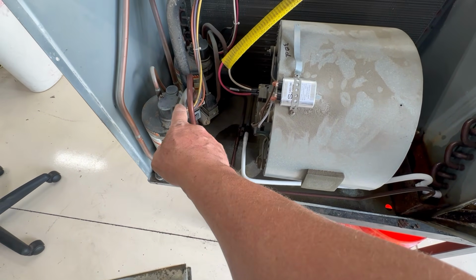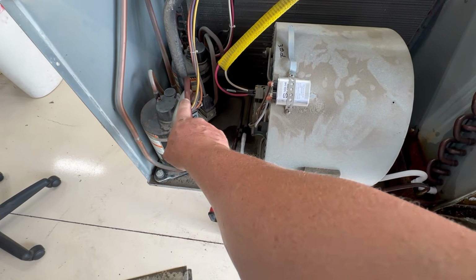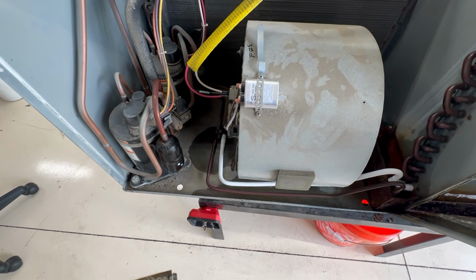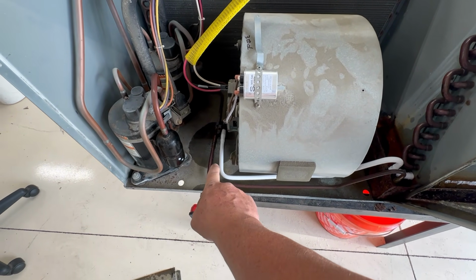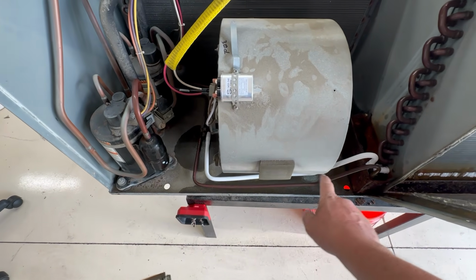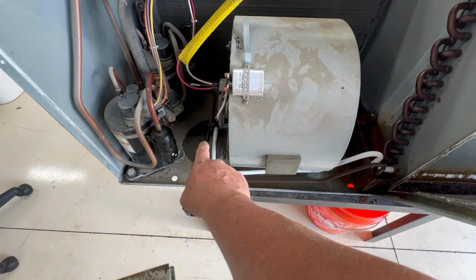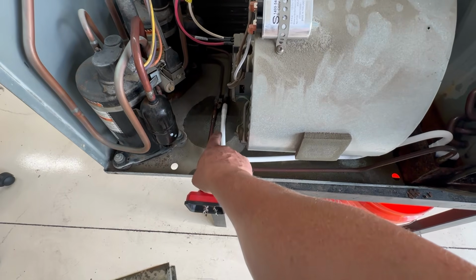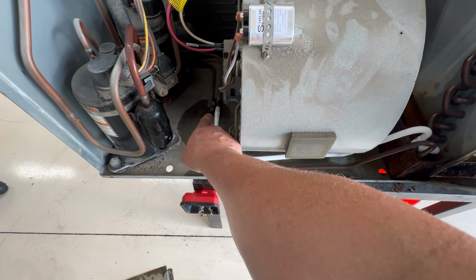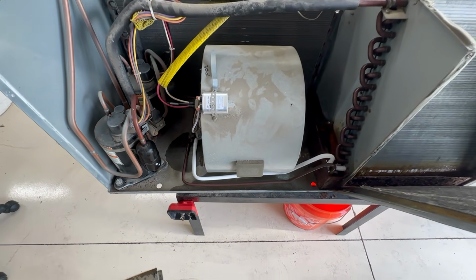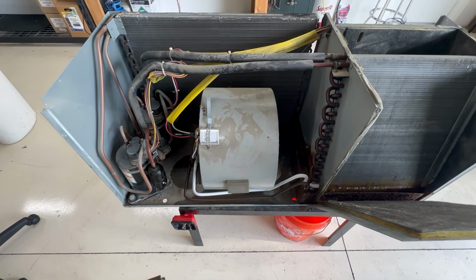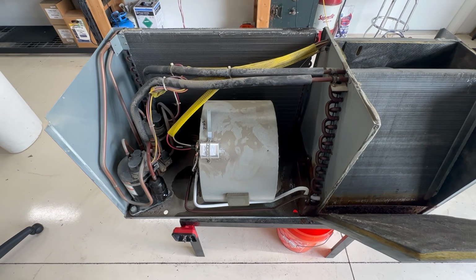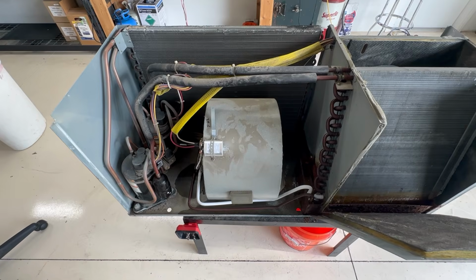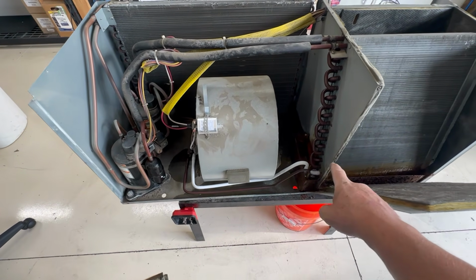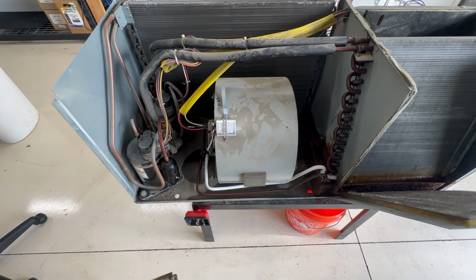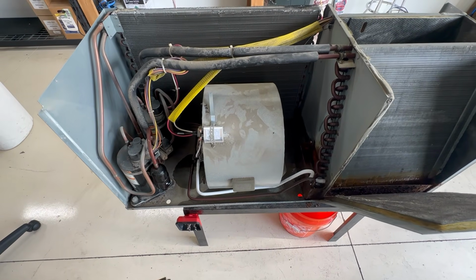Something in this circuit has gotten trash in it, and that Bi-flo valve is plugged enough that it's freezing. See how the other one's sweating, but it ain't froze up. There's a problem in that Bi-flo valve. So we're going to go in here and change it out. This thing has been running, but it's barely making a 17 to 20 degree differential. There's obviously a problem in that circuit, so we'll change that Bi-flo valve out and then retest this.